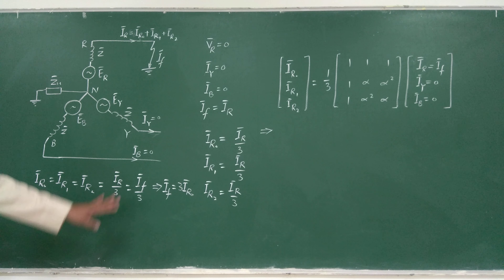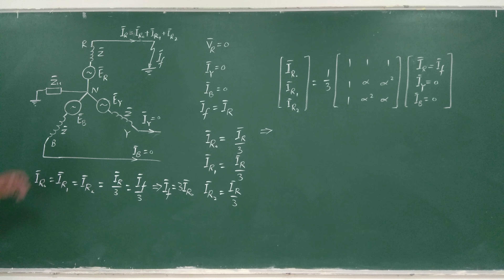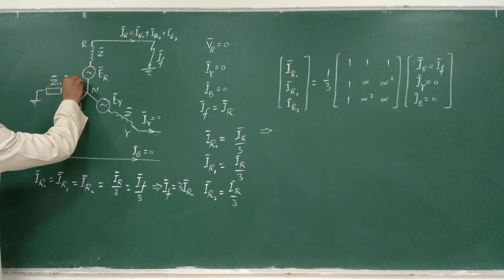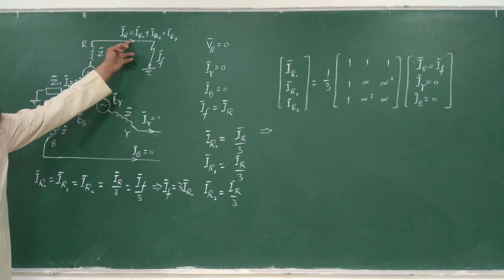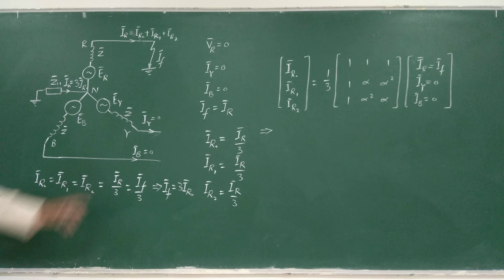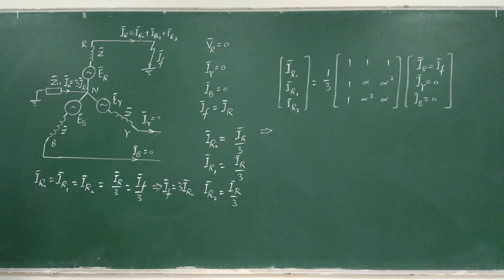So the fault current IF is three times IR0. That is also the current through the neutral IN. There is one loop for fault current from R to ground, then through neutral back to R. The magnitude of that fault current is 3 times IR0. We have now evaluated the zero, positive, and negative sequence currents for this SLG fault.